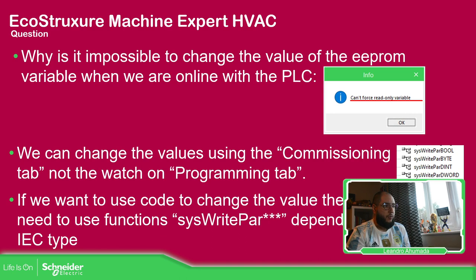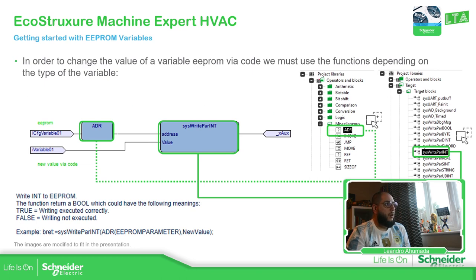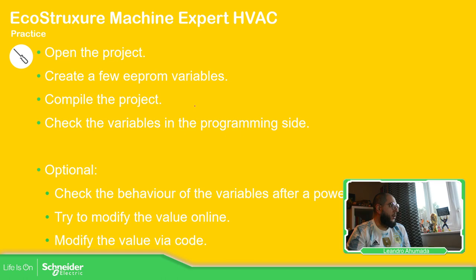To summarize how to use those functions: from Operators and Blocks, go to Miscellaneous to get the ADR operator — which gives the address of the EEPROM variable. Then from Target Blocks, use sysWritePar and select the correct variable type. Drag and drop it in, add the EEPROM variable address and the new value — which can be another variable or a fixed value — and the output is a Boolean. Then compile and create your variables.